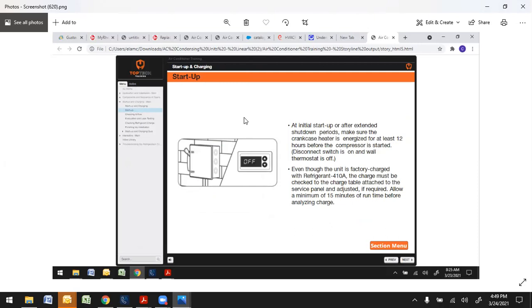Okay, now normal startup. On initial startup or extended periods of shutdown, they recommend that you have the crankcase heater energized for at least 12 hours before the compressor is started. That's probably not going to happen in the real world, but if you can, obviously power it up. Even though the unit is factory charged with 410A, the charge must be checked against the charge table attached to the service panel and adjusted if required.